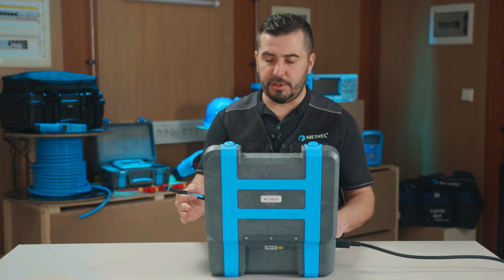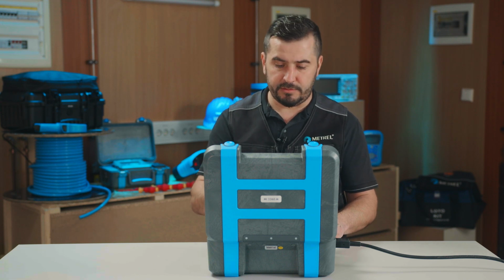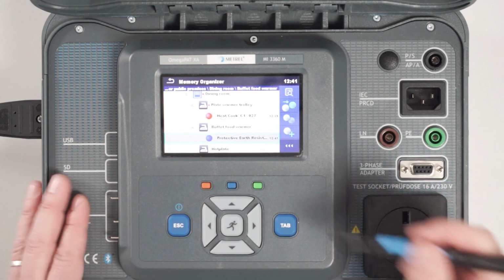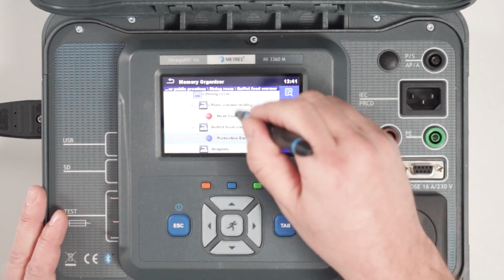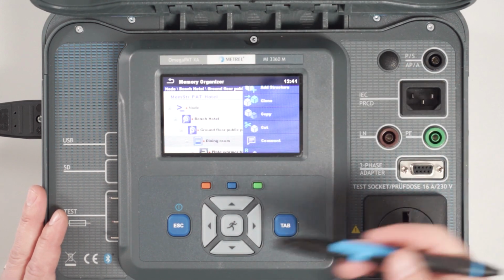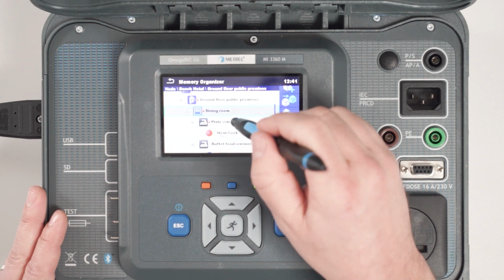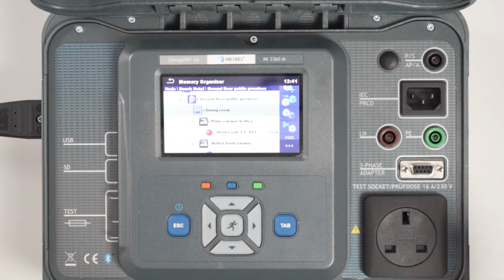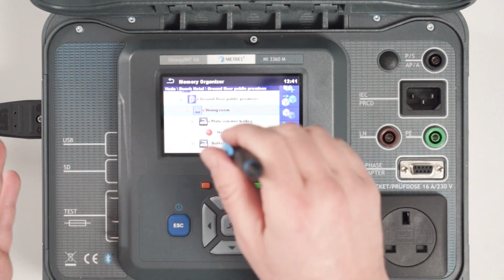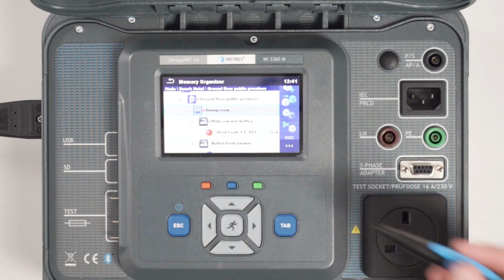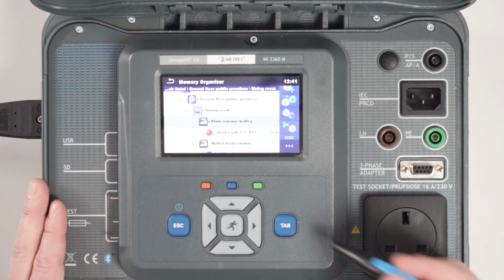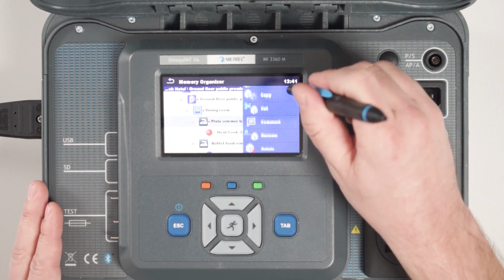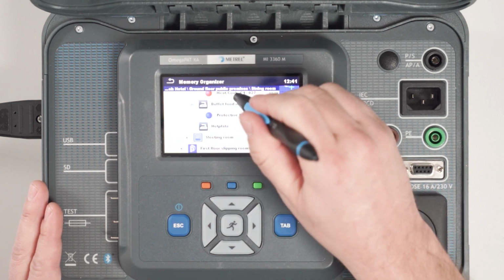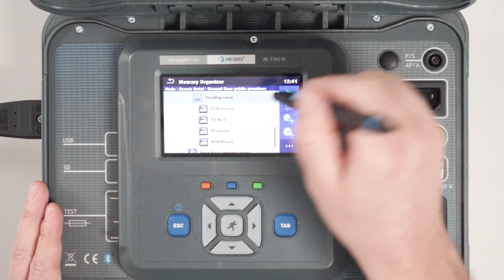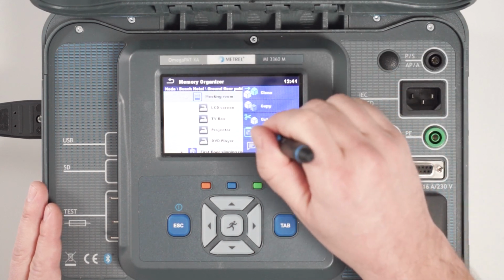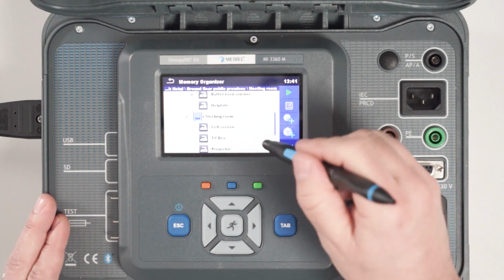So now we will simply execute this earth continuity test that we have just added. The measurement will again fail because we do not have anything connected on the device itself. We can save, or we can even add a comment for the particular measurement itself. We have also the option here to move these appliances from one location to another. So for example, if the appliance was today in this room, and the next time we come around it is located in the other room, we can select here this appliance. We simply go here under the cut option and we move the appliance inside the meeting room, for example, and we say here paste. So this means that the appliance is now in the other location.